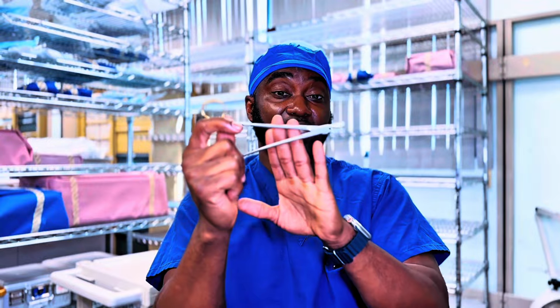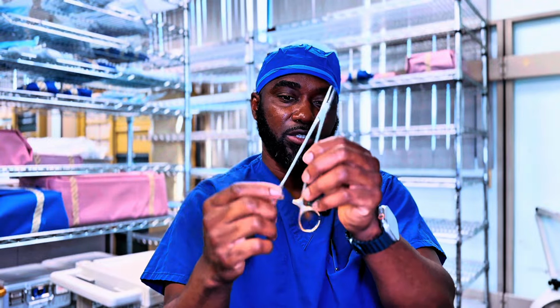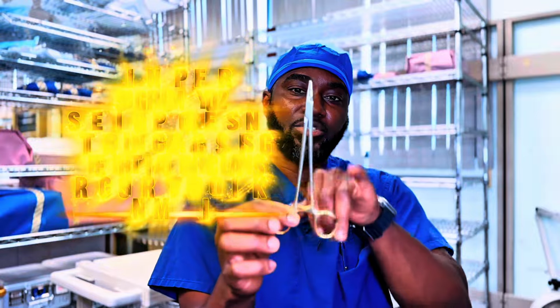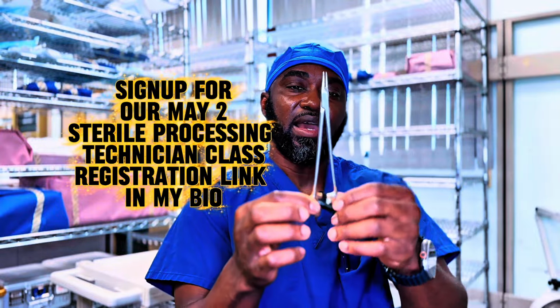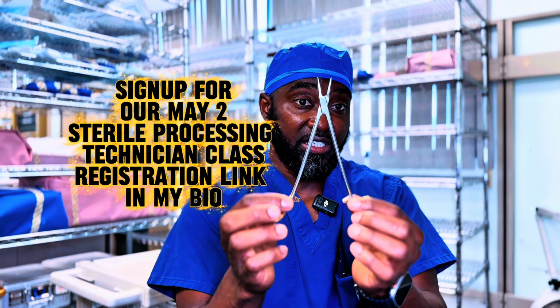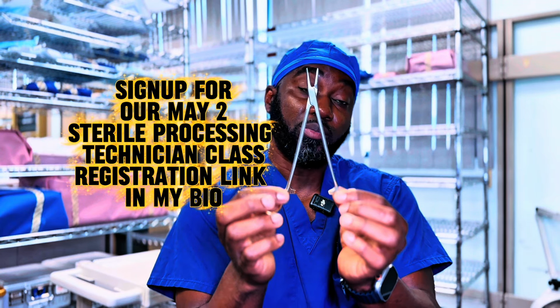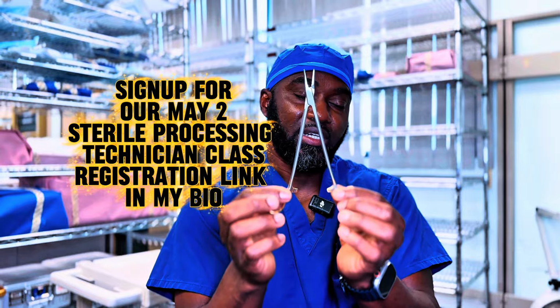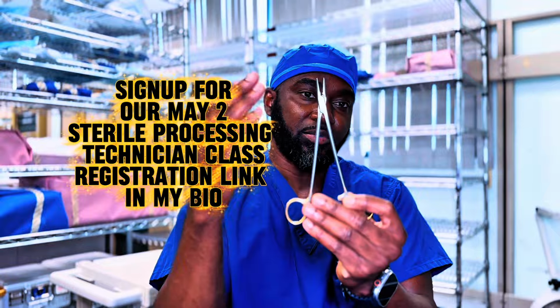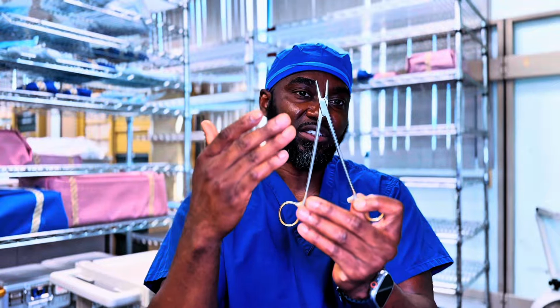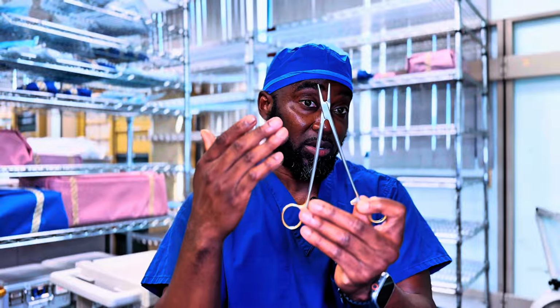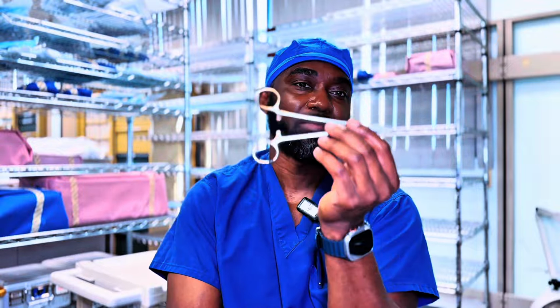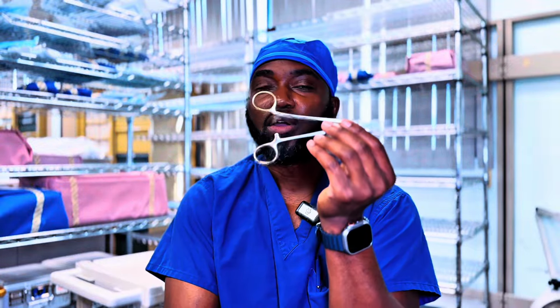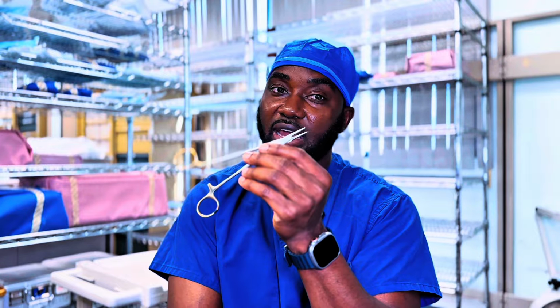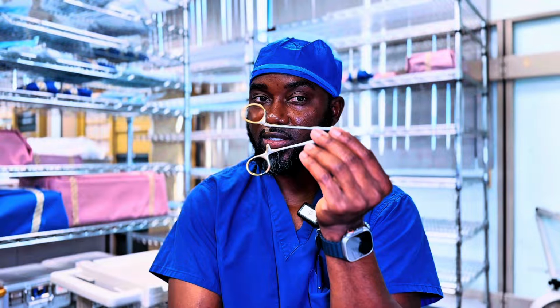The manufacturer tests this device, which is a Mayo-Hegar needle holder, and at the independent lab, this was soiled up with microorganisms and sterilized at 270 degrees Fahrenheit for 2 minutes for 3 consecutive times. After the sterilization, the instruments will be tested for the presence of microbes. If there is no microorganism on here, the same process used to sterilize the instrument, the packaging method used to sterilize this instrument, will now be recommended to the end user who purchased this medical device.